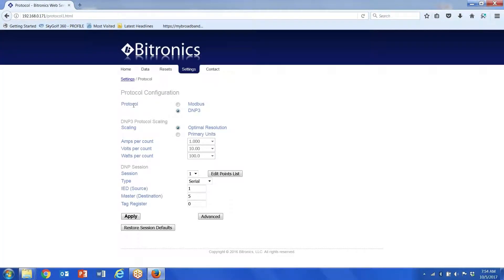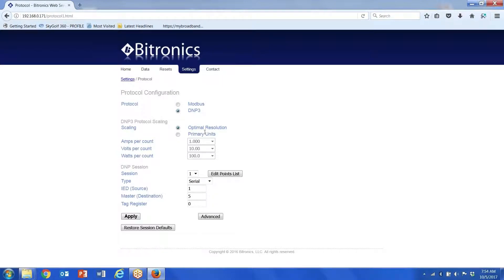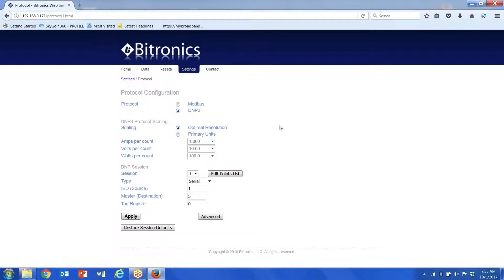Click on the protocol option. I have two options: Modbus and DNP3. No matter which one I select, I also have the ability to select optimal resolution, which is HD counts like -32,768 to +32,767, or I can select primary units, which would look very similar to a Schweitzer relay using fast messaging.